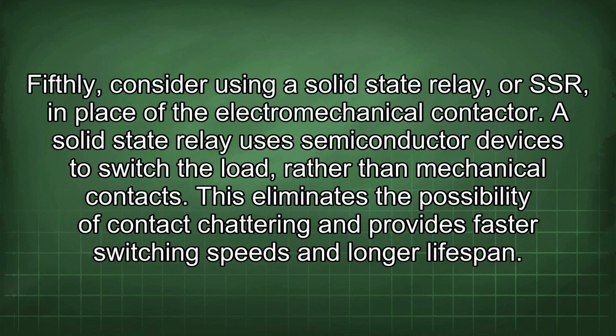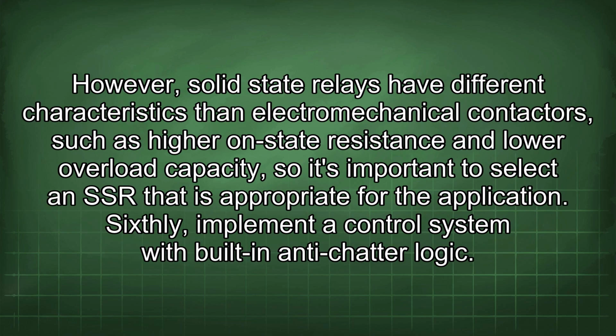Fifthly, consider using a solid-state relay, or SSR, in place of the electromechanical contactor. A solid-state relay uses semiconductor devices to switch the load, rather than mechanical contacts. This eliminates the possibility of contact chattering and provides faster switching speeds and longer lifespan. However, solid-state relays have different characteristics than electromechanical contactors, such as higher on-state resistance and lower overload capacity, so it's important to select an SSR that is appropriate for the application.